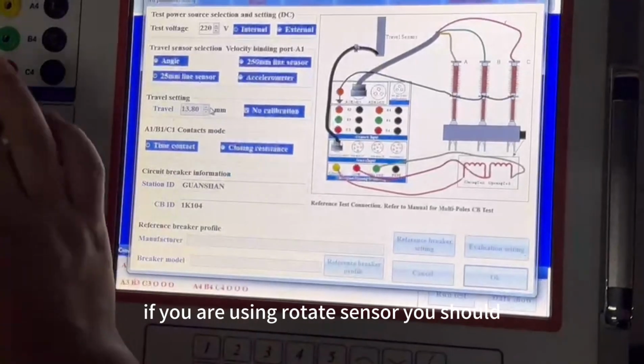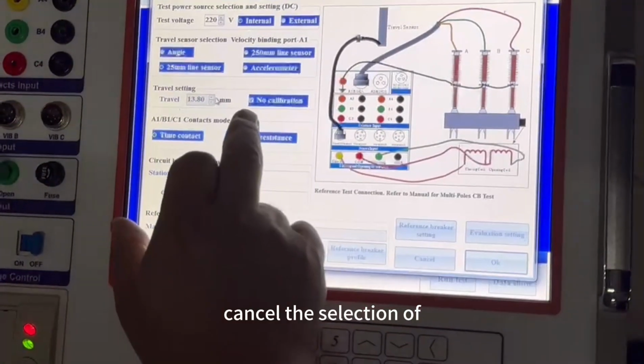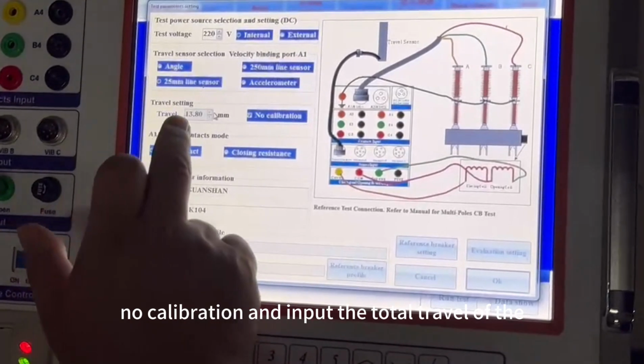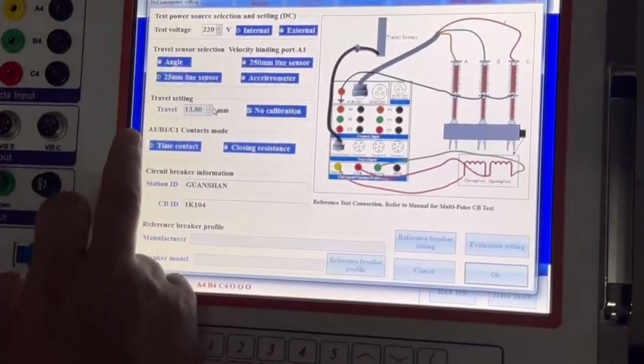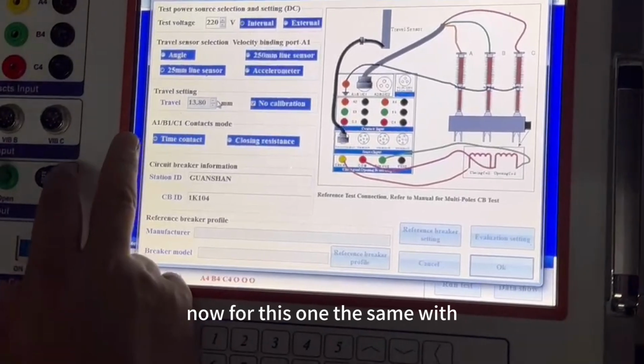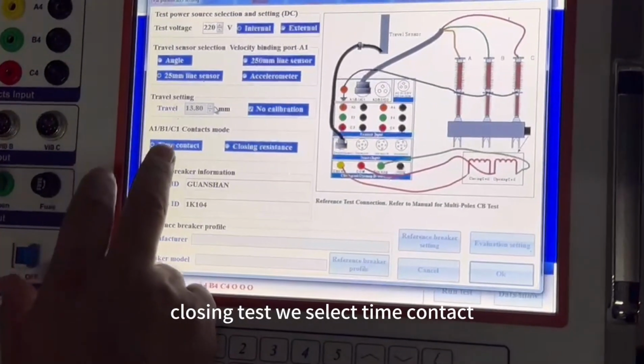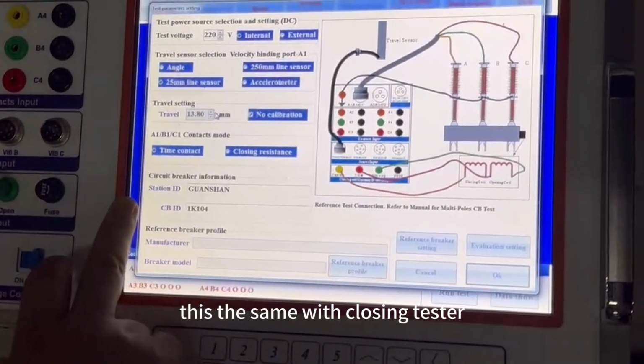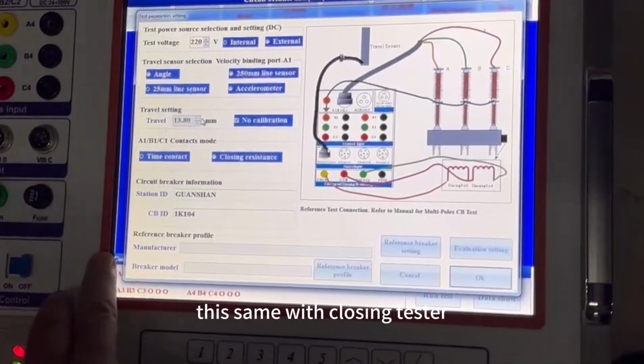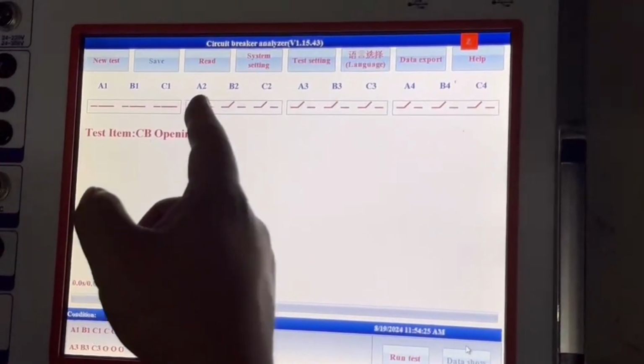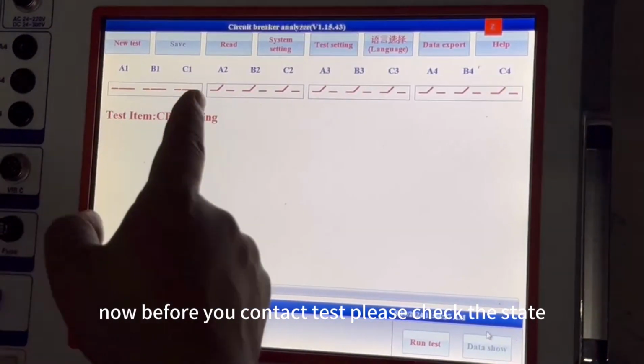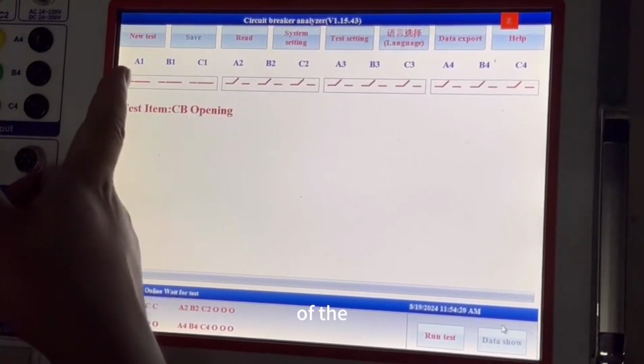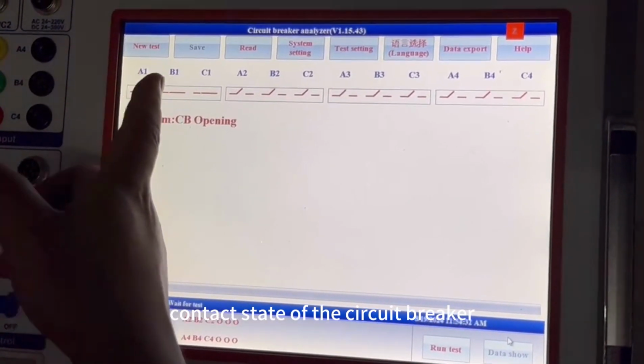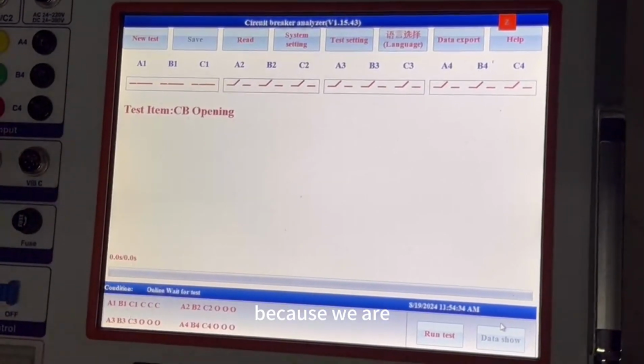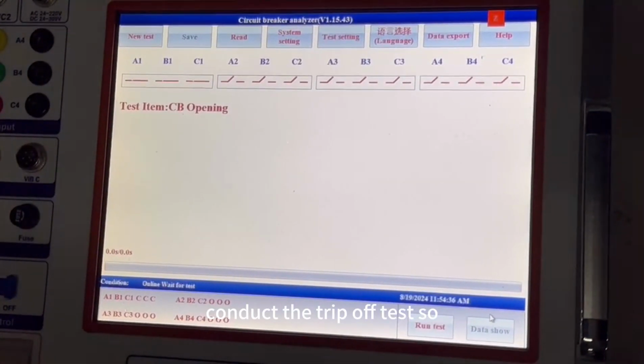If you are using the rotary sensor, you should cancel the selection of no calibration and input the total travel of the circuit breaker. Now, for this one, the same as the closing test, we select time contact. This is the same as the closing test. Now, before you conduct the test, please check the contact state of the circuit breaker, because we are conducting the trip off test.